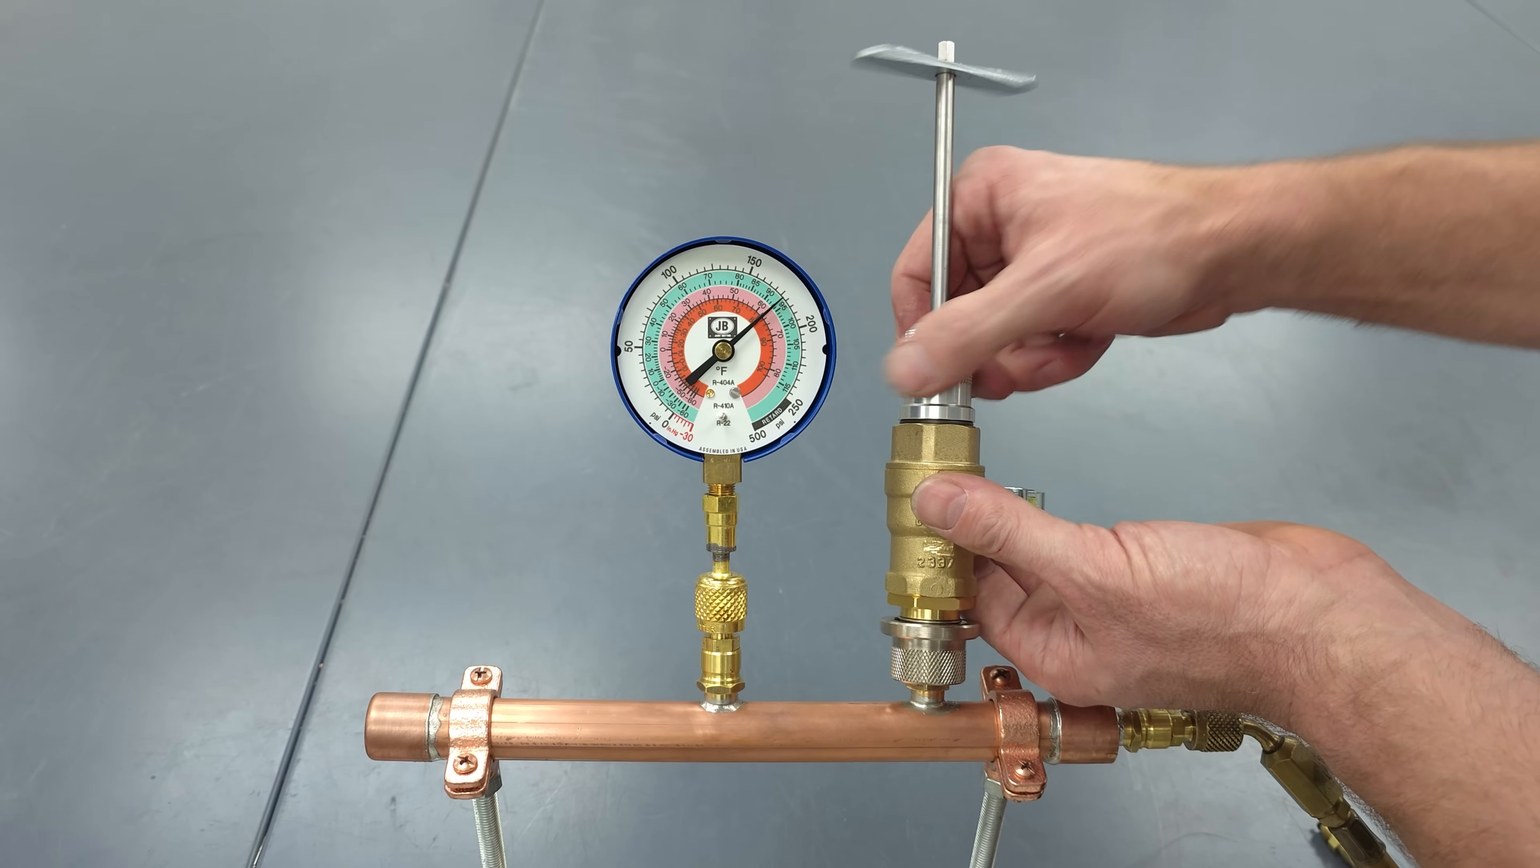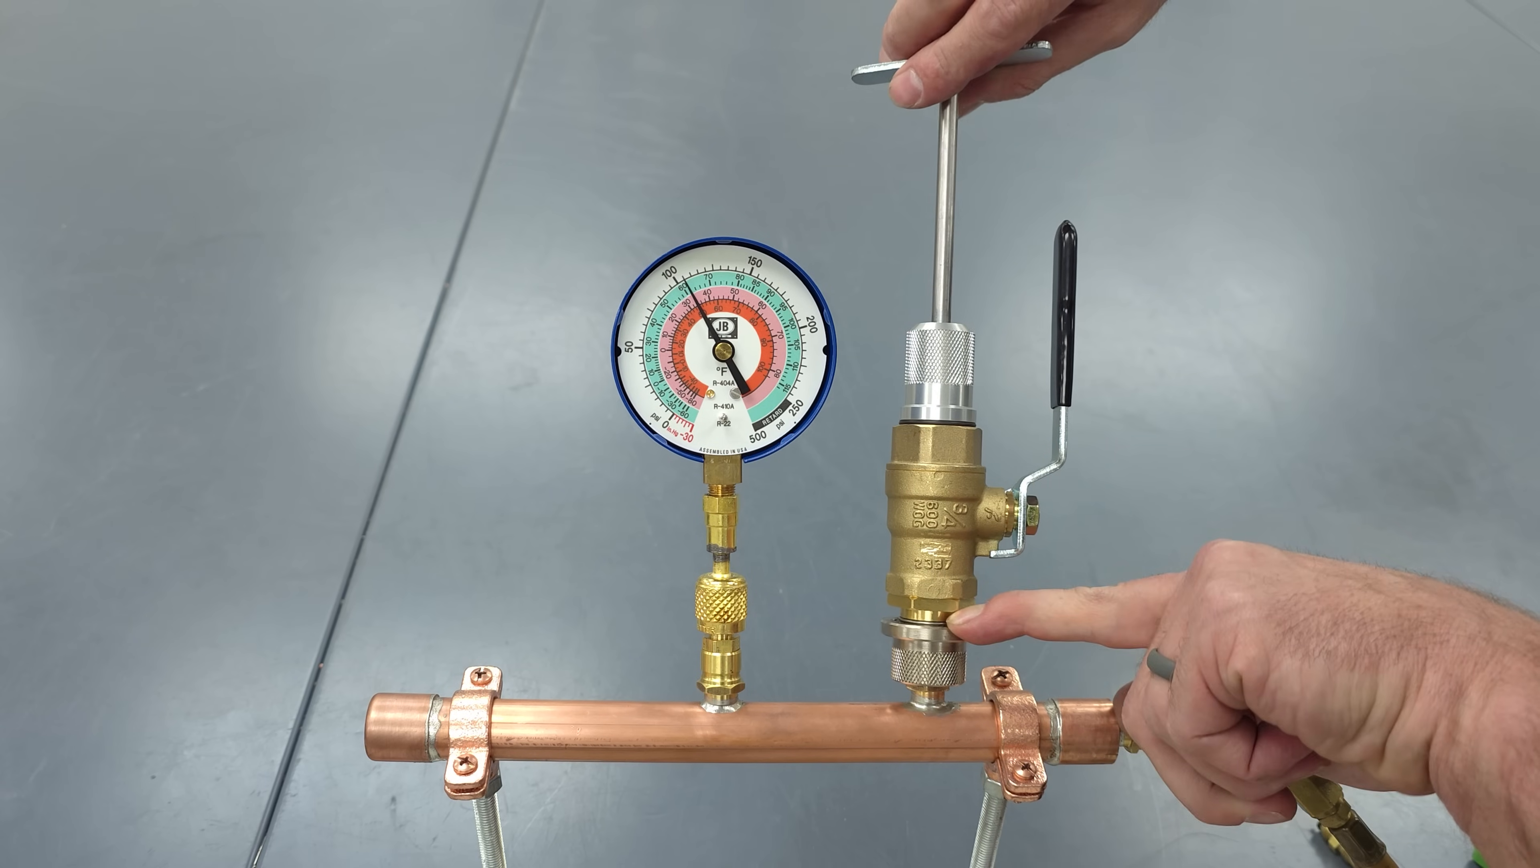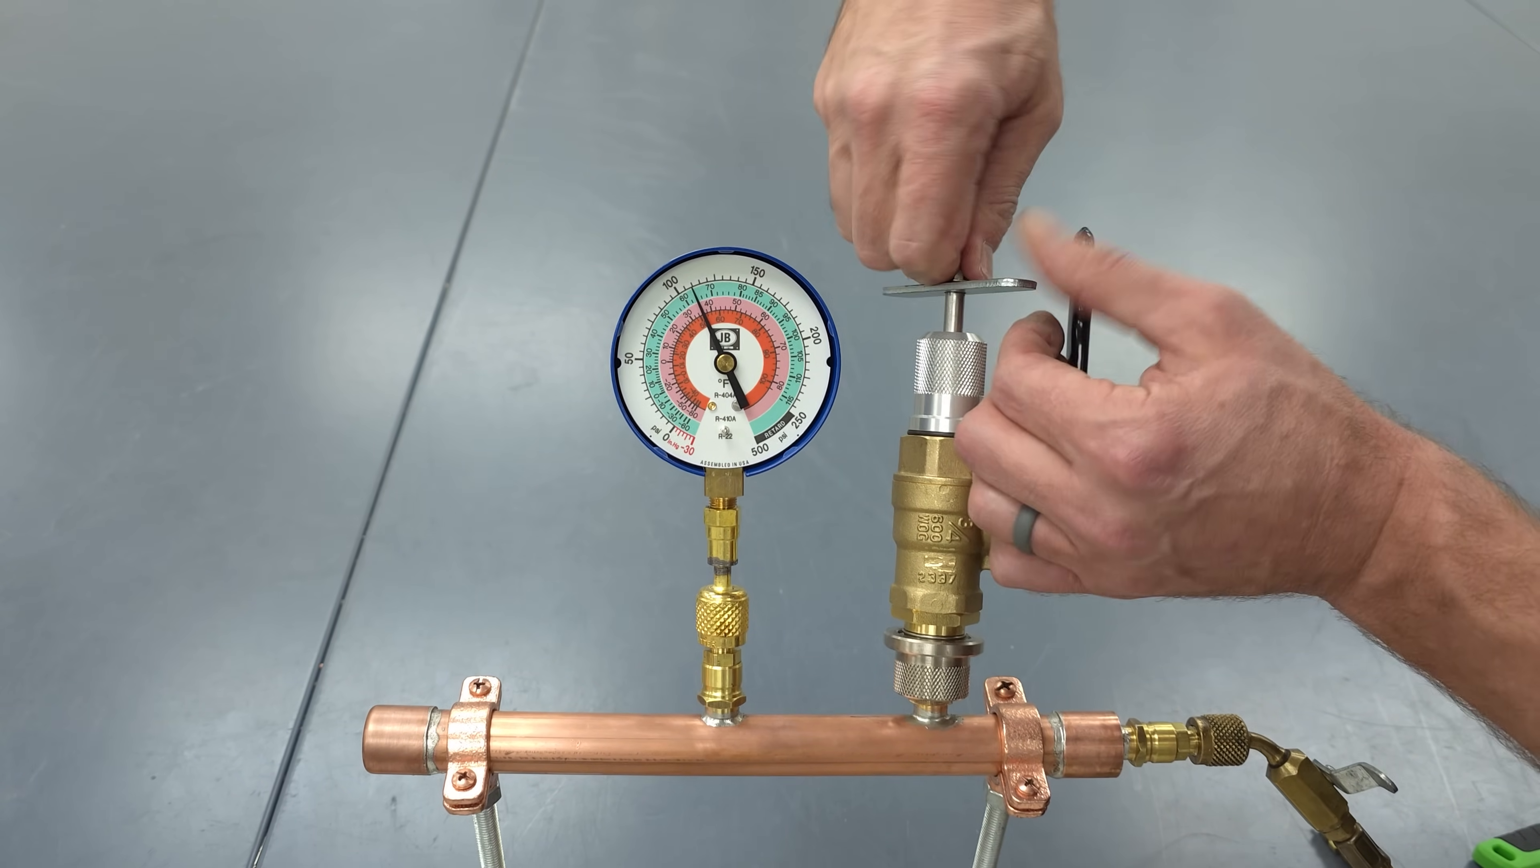Now when we tighten this in we want to open the valve because we want to make sure to purge any air that's in here out if this is refrigerant. And so now we can go ahead and open this up. Once again you want to make sure that this does not get bumped during this procedure and we can go ahead and push this in and turn it clockwise.